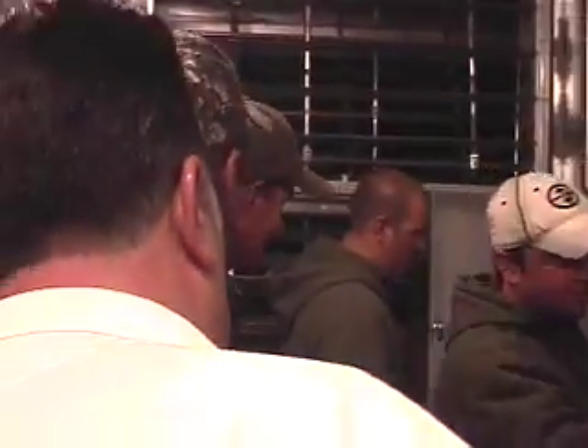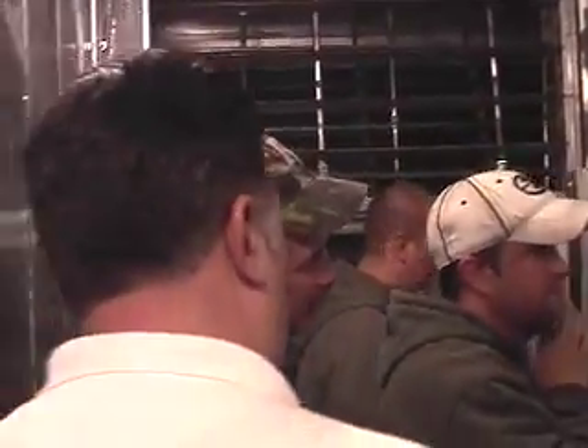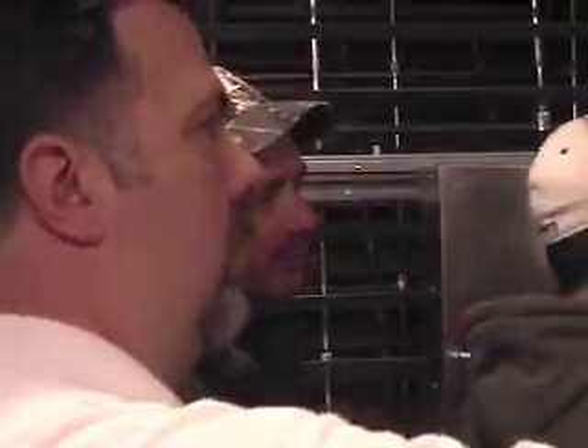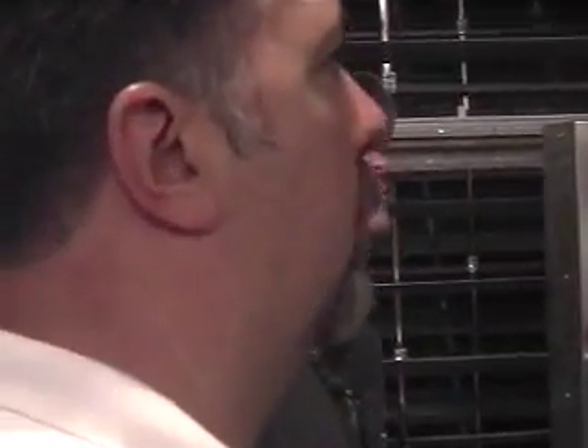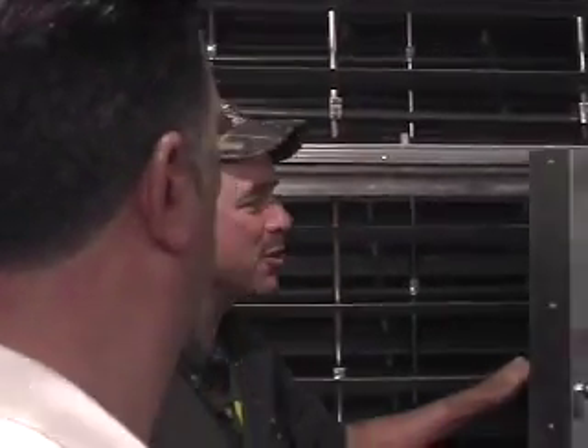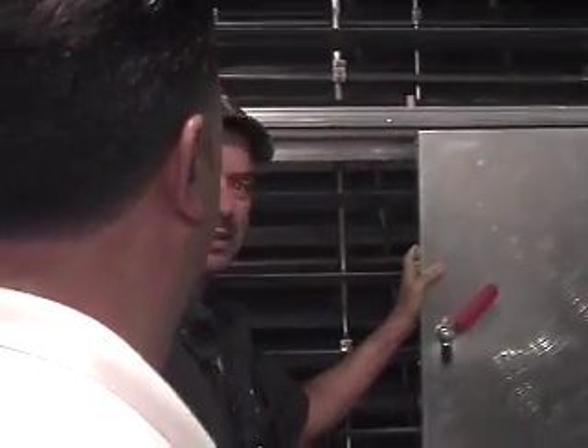Here's the other dampers. You can see, so when this side's closed, the other side of the coil is closed as well. All three dampers operate off the same signal, just to position. So you're either one side or the other. See your coil in there? This is your coil section, kind of a V shape, so it looks like this on the other side as well. It's making a lot more sense.